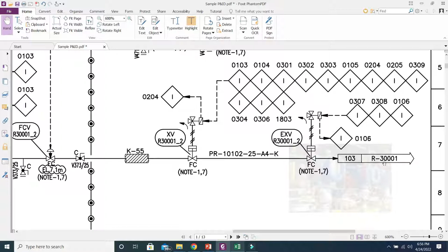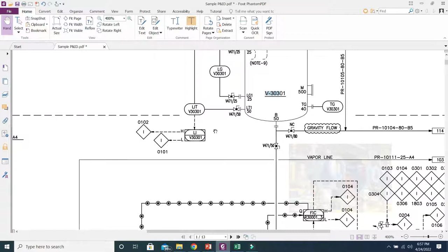Then equipment number. Equipment number means if your instrument is on any equipment, then you have to provide the equipment number. This level transmitter is on this equipment, so for this tag you need to provide the equipment number. But this alarm is not on the equipment, because these are soft items and not physical items, so we do not need to provide the equipment number for these alarm items. If any instrument, like this pressure gauge, is not on the equipment but on a line, then for this tag we do not need to provide the equipment number; we can simply provide the line number.